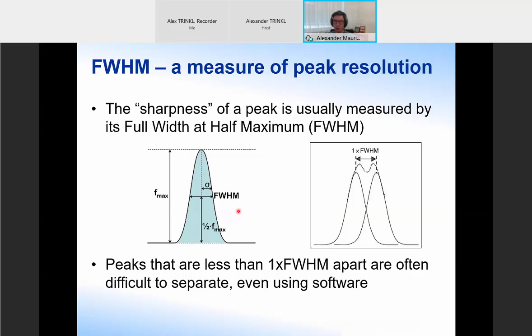Again, a parameter that you would like to be low, you would like it to be small. That means that the resolution is good. You have very narrow, nice peaks. Let's look at a comparison of the same sample spectrum on three different detector types. So here you have the same sample measured on a high purity germanium detector, which is blue, on a lanthanum bromide detector, which is the red one, and the sodium iodide detector, which is the green one.